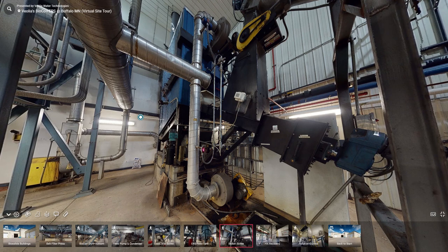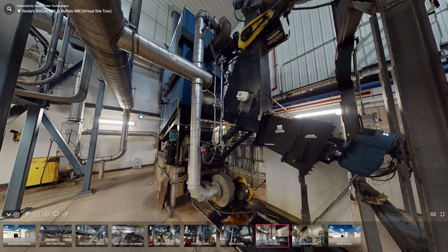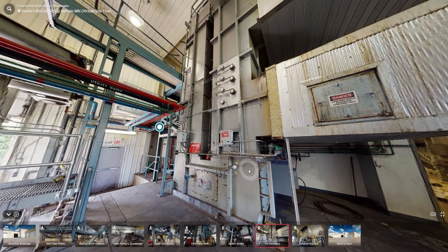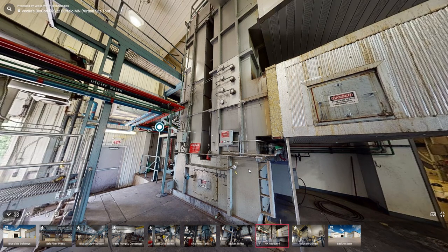The flue gas from this process is relatively hot, and by using a heat recovery heat exchanger — either air-to-air, as you're seeing here at this facility, or an air-to-thermal oil system — you're able to recapture the heat leaving the flue gas and repurpose it to heat the dryer, making this whole process net neutral or net positive depending on the type of sludge that's being processed.